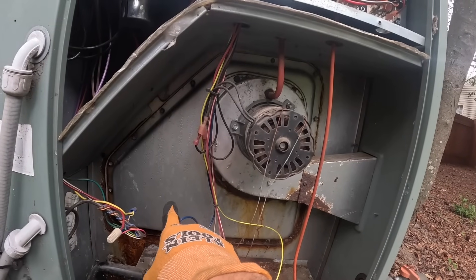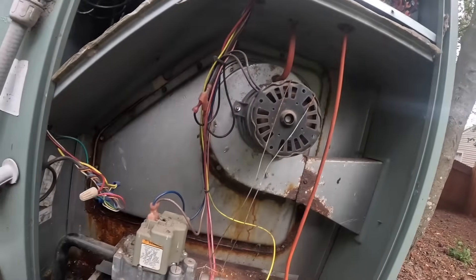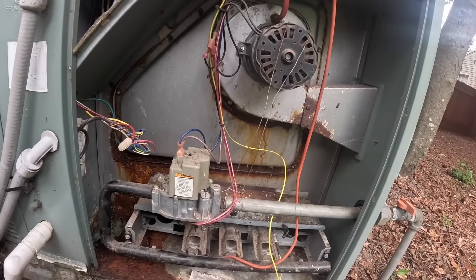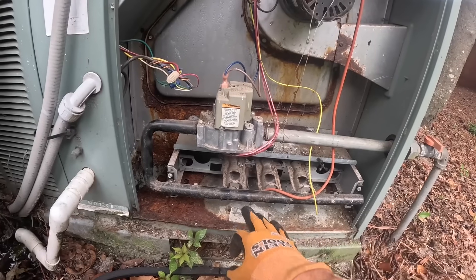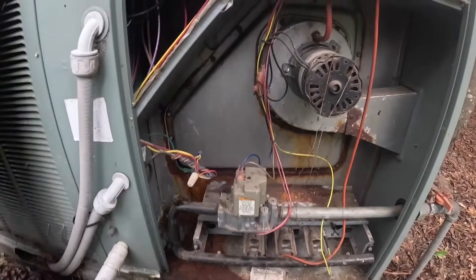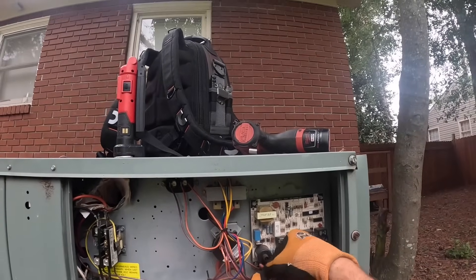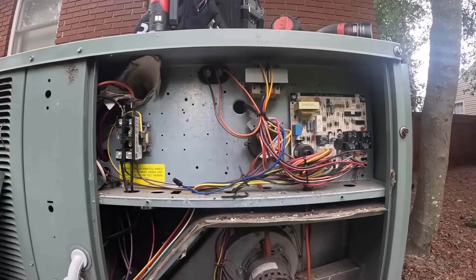So: draft motor, this little plenum here that connects to the flue pipe — what I call a flue box cover or collector box — that is severely rusted. Heat shield, probably burners, and this rusted-out plate on the bottom that I haven't been able to find. Now that thing cannot fire. Your air conditioner should work better, but you ain't gonna have no heat.